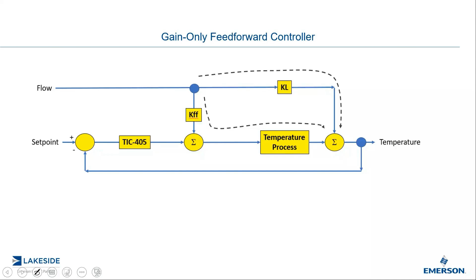How do you calculate it? KFF equals minus KL over KP - the ratio of the load gain to the process gain. Note the negative value as well, because in our example an increase in product flow causes a decrease in temperature. That's because there's less residence time going through the heat exchanger, so less heat is absorbed, and the temperature drops.